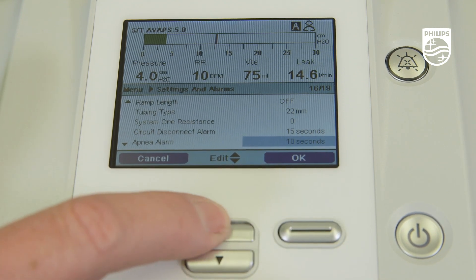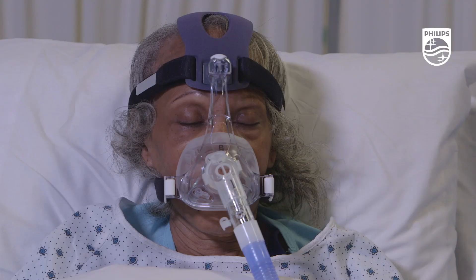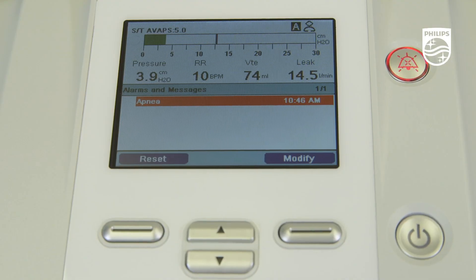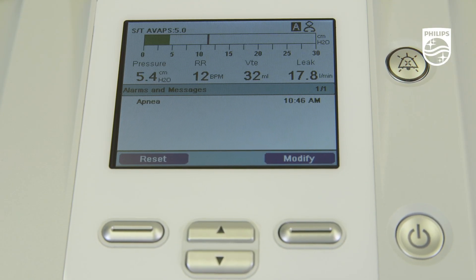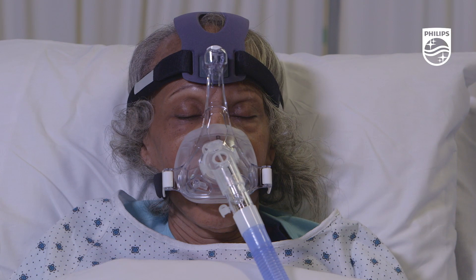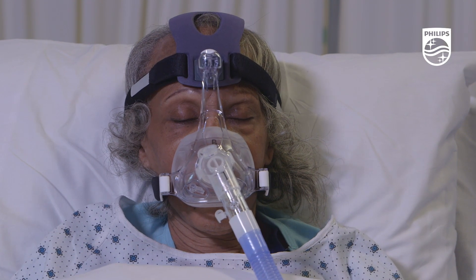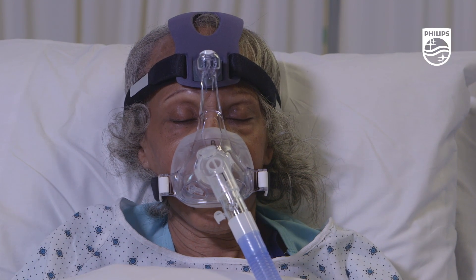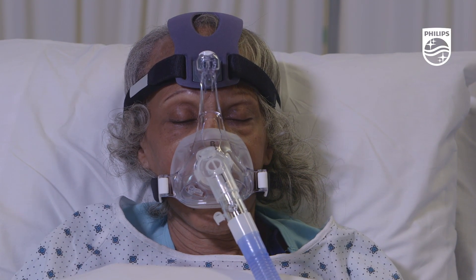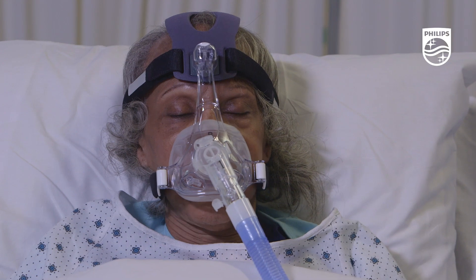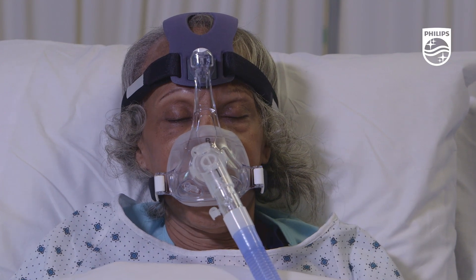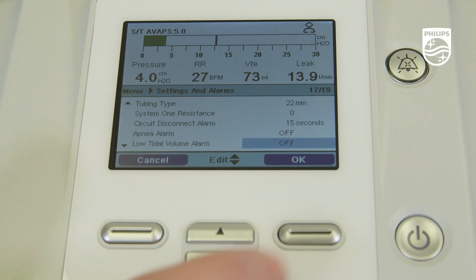Next is the apnea alarm. This high priority alarm occurs when the patient has not triggered a breath within the time specified in the alarm setting. The alarm will automatically terminate when two consecutive patient breaths are detected that meet the apnea alarm time setting.